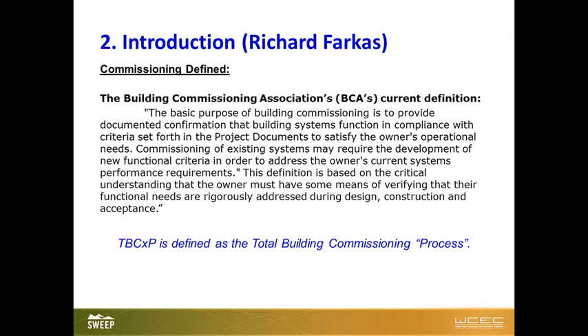I want to reiterate that commissioning of existing systems may require the development of new functional criteria in order to address the owner's current system performance requirements. So what we're saying is there's an understanding that buildings change, utilization changes. For example, we can have a conference room that's subdivided into offices. Now all of a sudden you've affected the airflow, people are uncomfortable, or you put heat-producing equipment in the room and now you're burdening the system. There's any number of possibilities of things that could happen, but that's what that's referring to. So this definition is based on the critical understanding that the owner must have some means of verifying that their functional needs are rigorously addressed during design, construction, and acceptance.